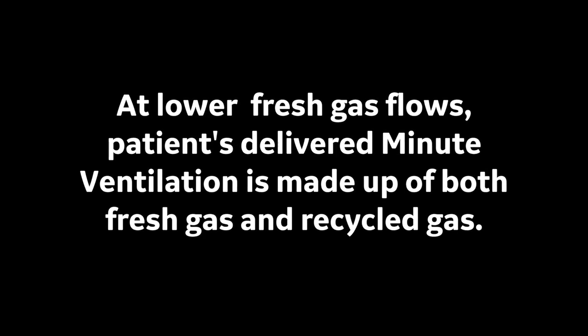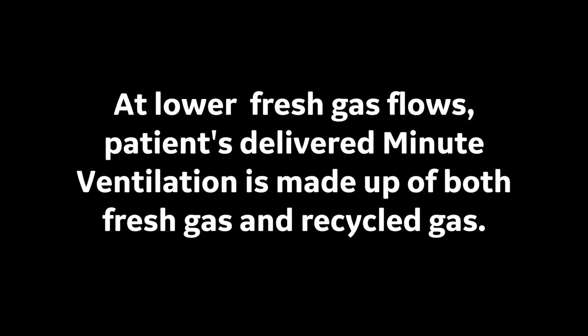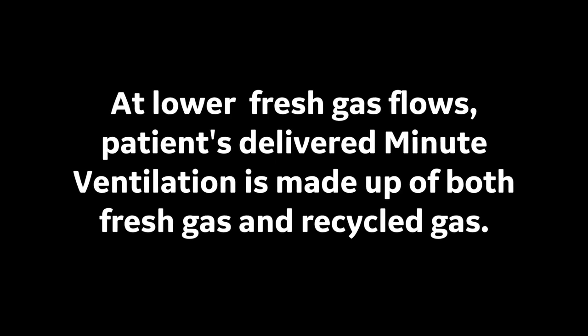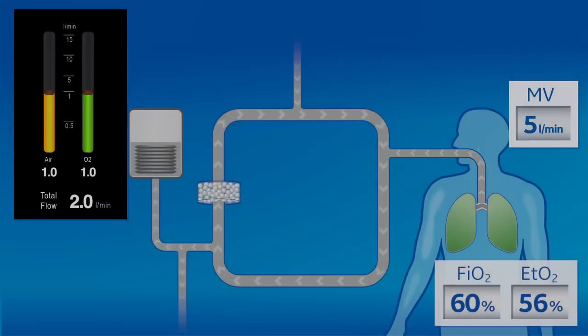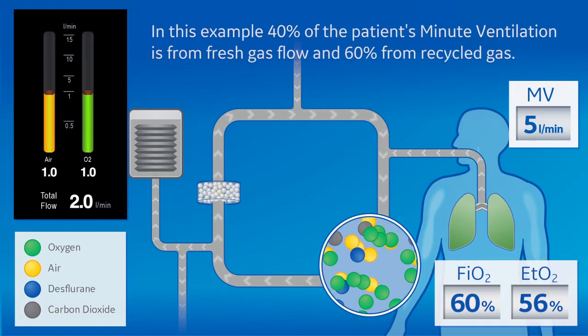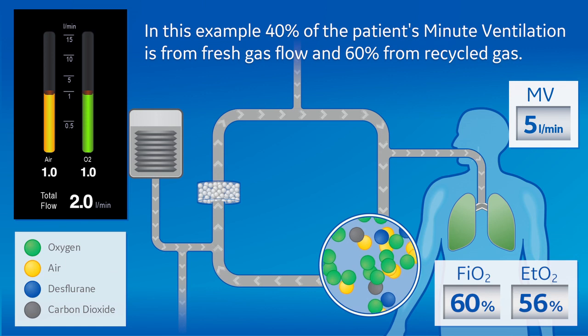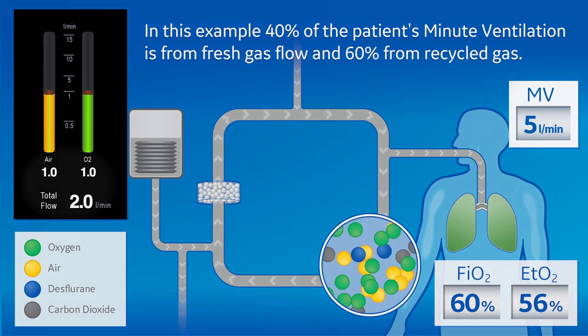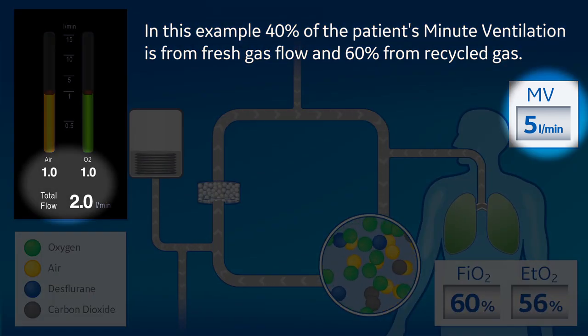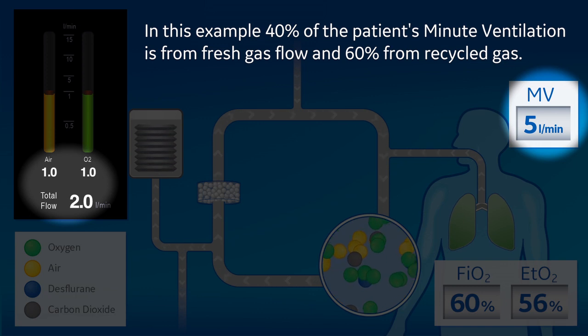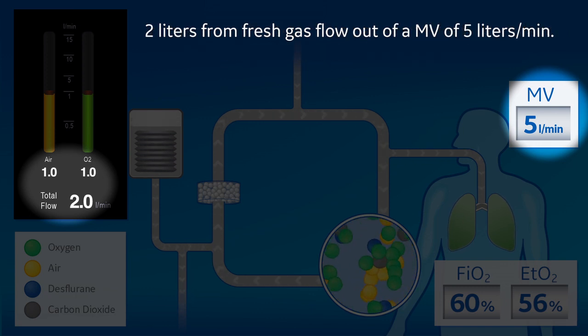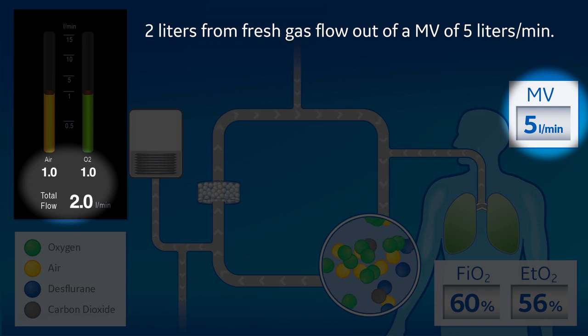At lower fresh gas flows, the patient's delivered minute ventilation is made up of both fresh gas and recycled gas. In this example, 40% of the patient's minute ventilation is from fresh gas flow and 60% from recycled gas — 2 liters from fresh gas flow out of a minute ventilation of 5 liters per minute.